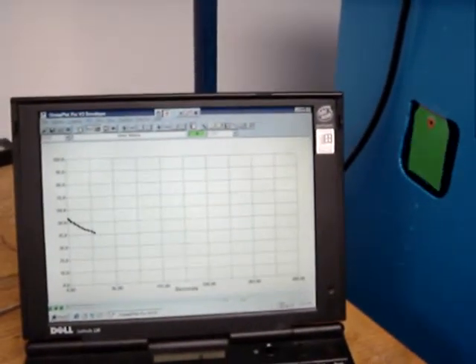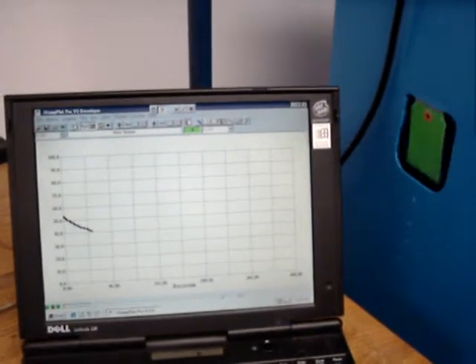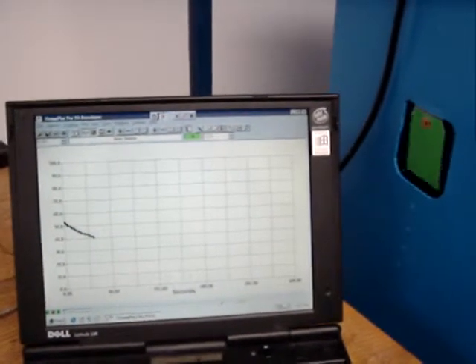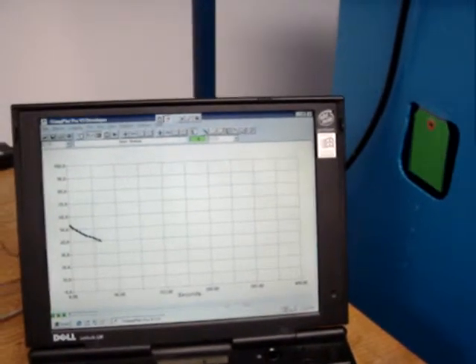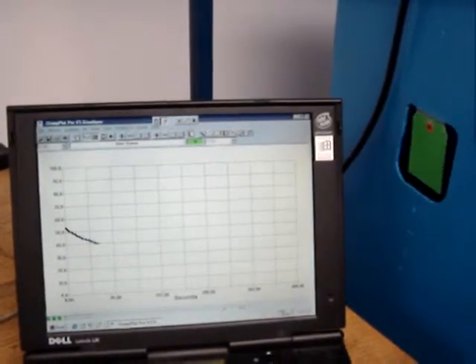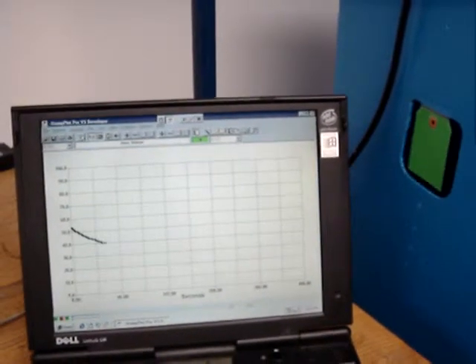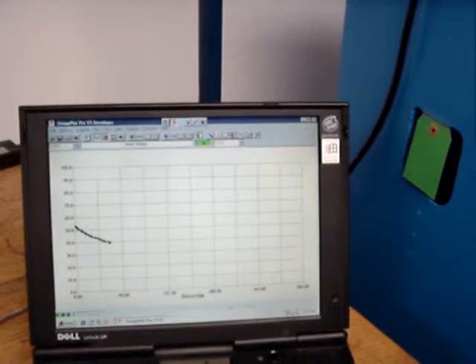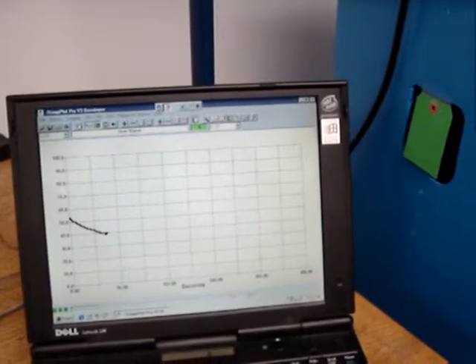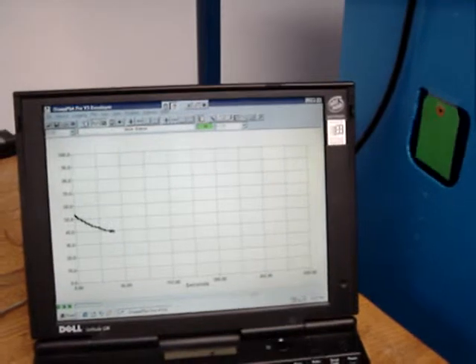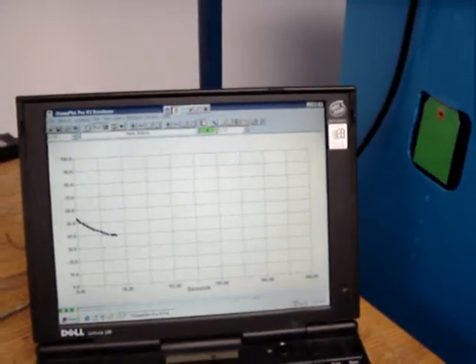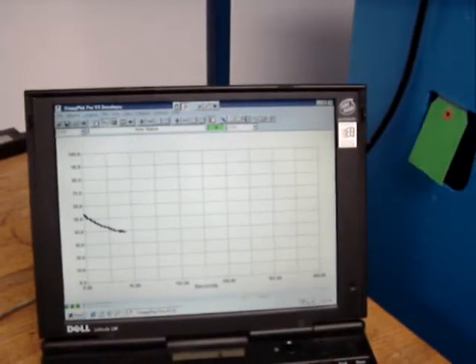So as it modulates that fan, you can see the flap start to go to the neutral position, which would be mostly straight down, and you can see that the speed of the fan is decreasing as it's trying to find that CFM balance point, where the exhaust fan is matching the CFM of the servers. So we'll let that go until it's pretty much balanced. Which right there is actually pretty close.